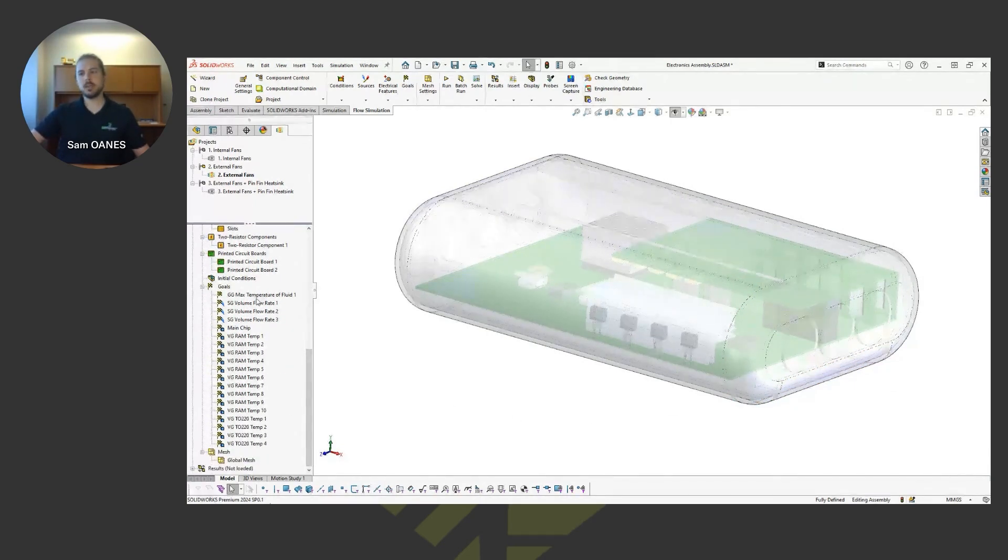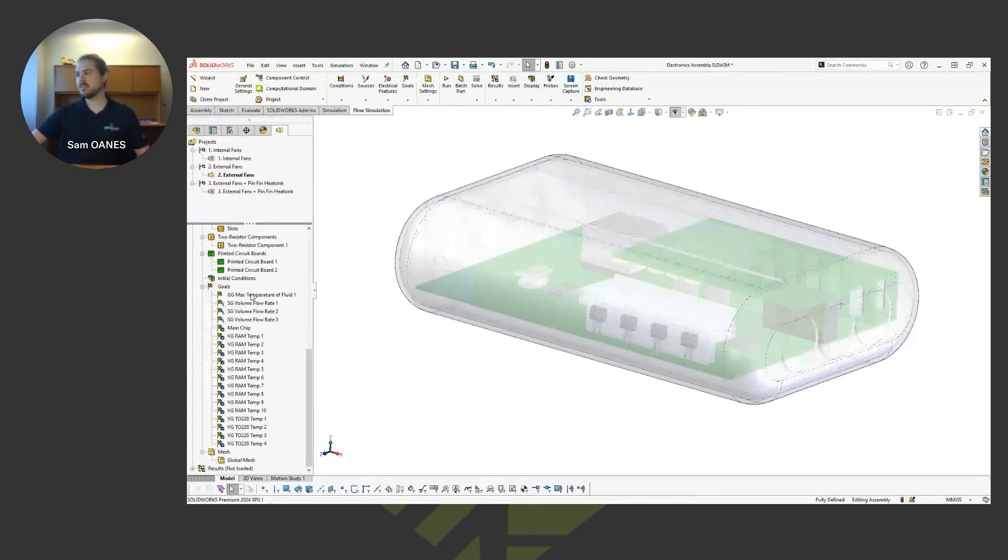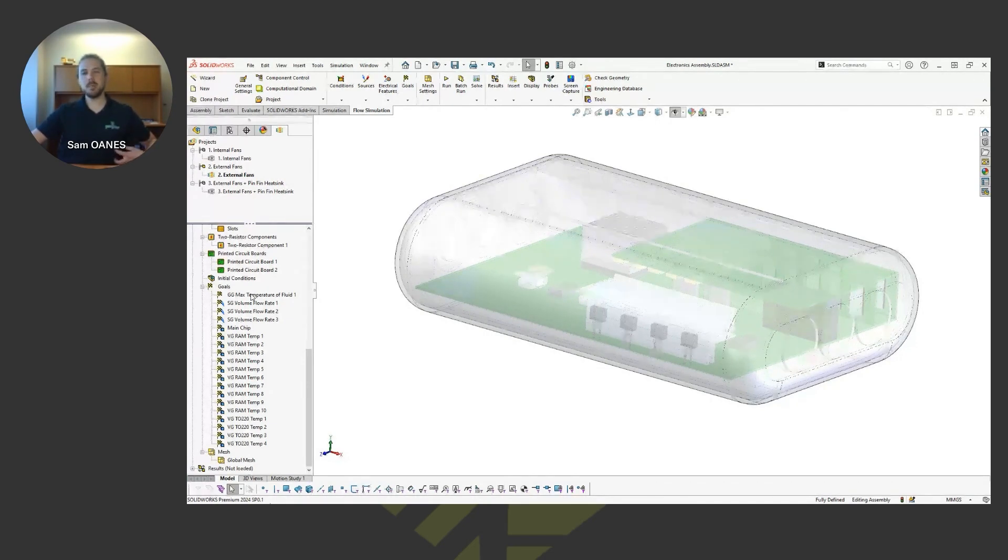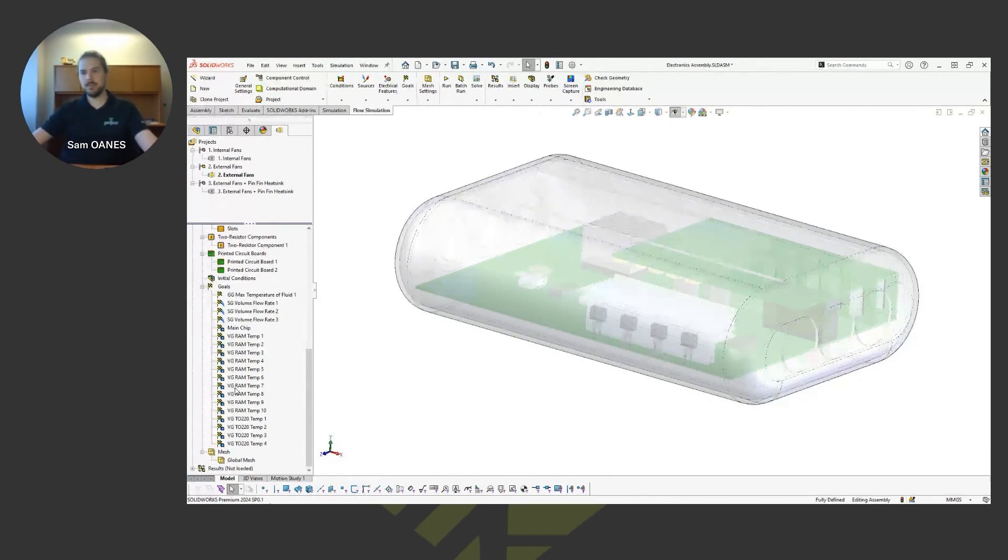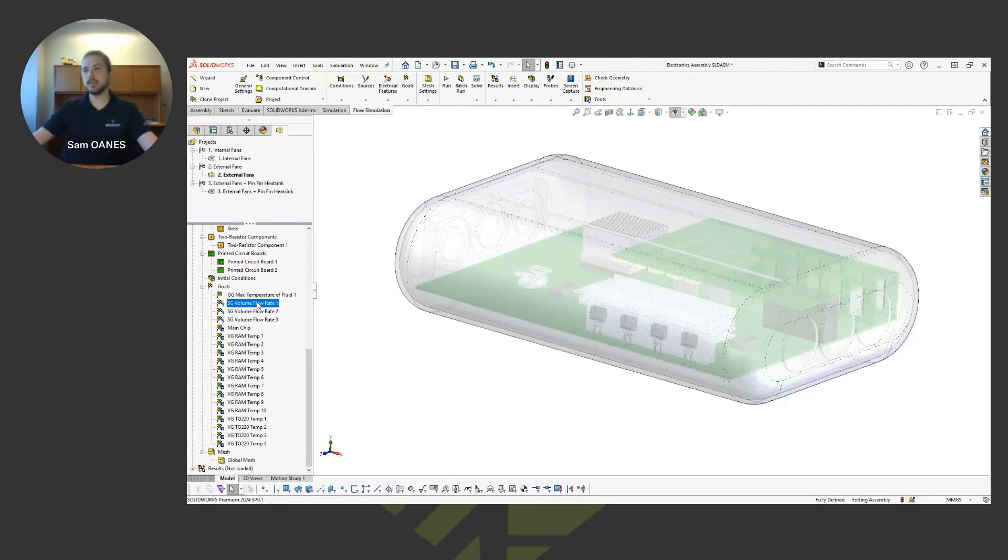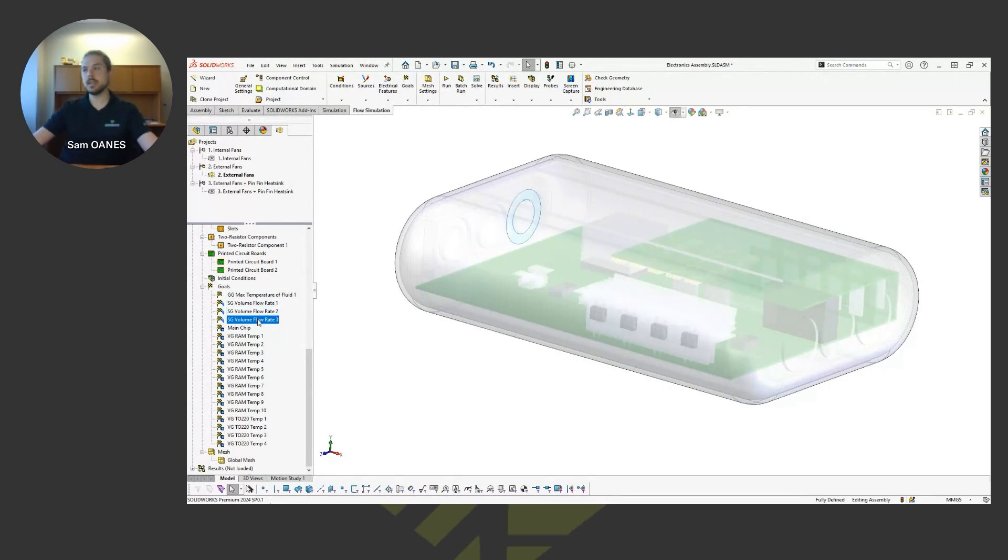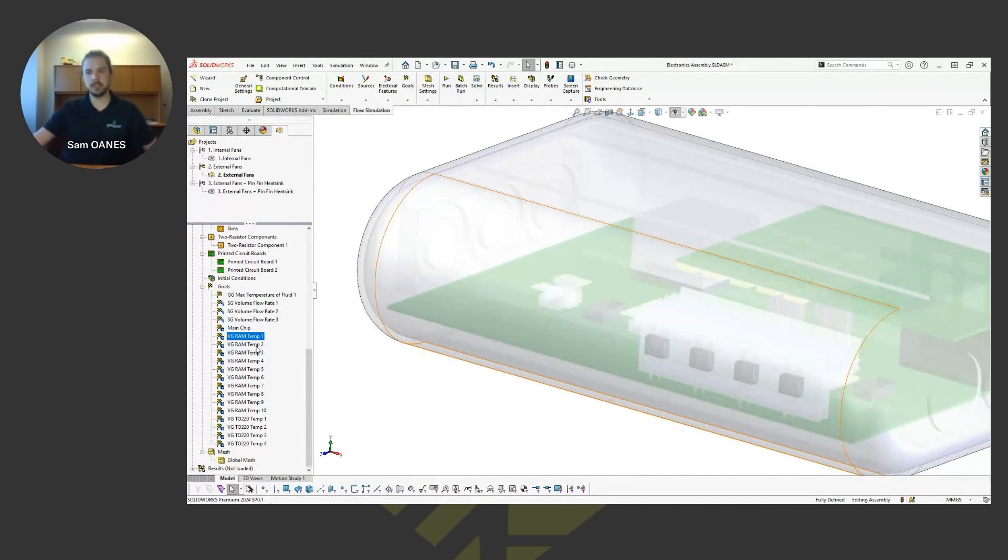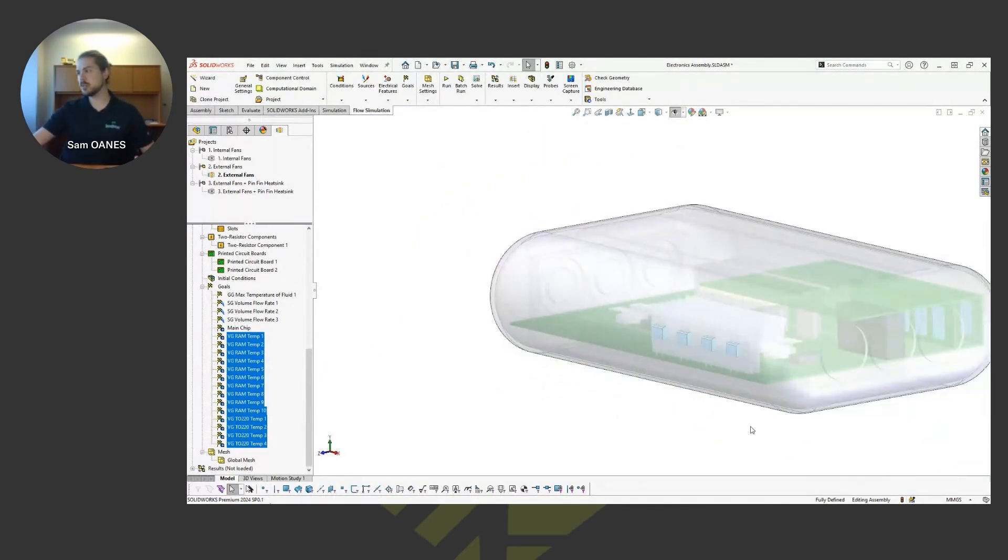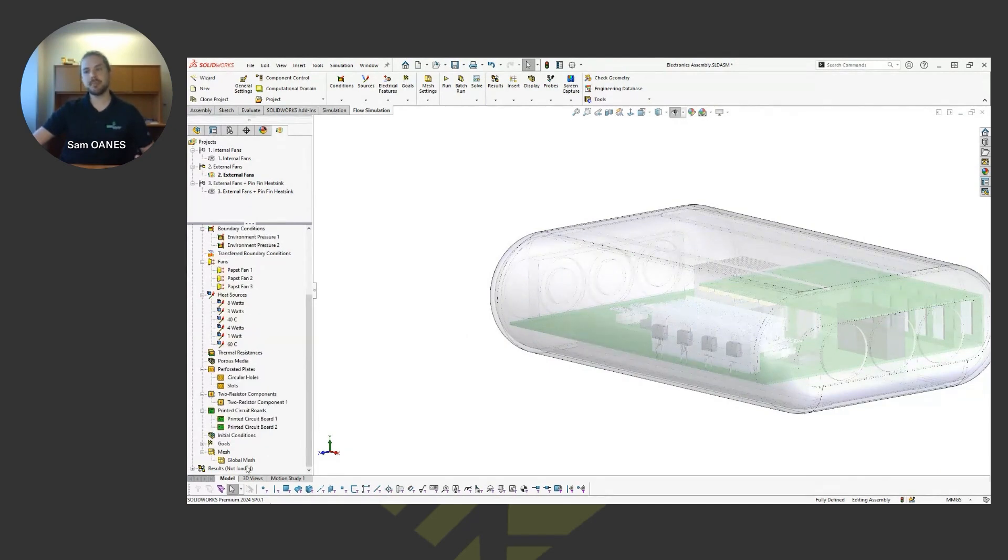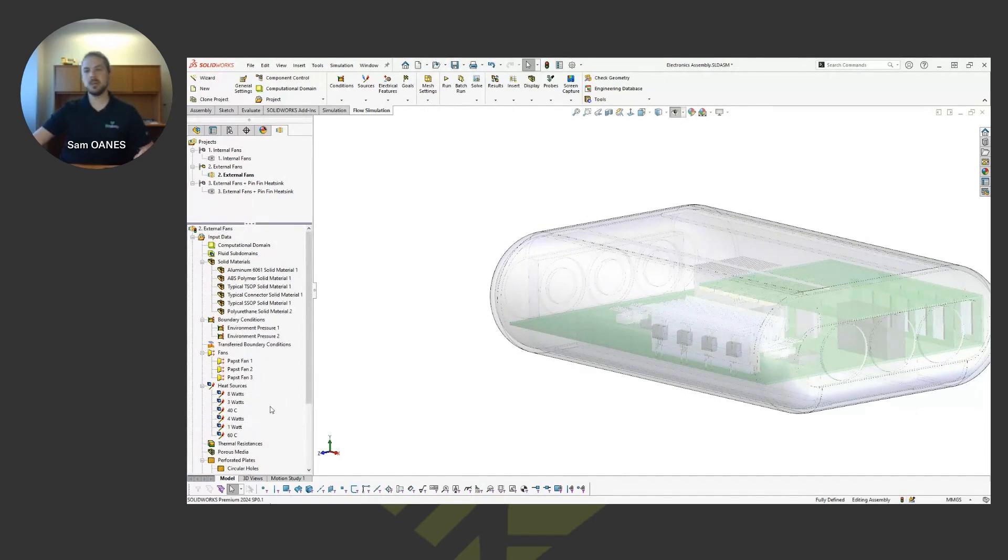After that, we set our goals. I like to describe these as pointing the solver in the right direction. We can think of these as sensors as well. The automated convergence I was mentioning happens with these goals - they define what our convergence criteria is. I've got some temperature goals, some flow rates on those fans. That main chip, I'm tracking the temperature on that, as well as all the temperature on our electric components that we don't want to be getting too hot. It's a great way to track data as well. After that, we let the study run, let the computer do its thing. Now we start doing some post-processing and looking at plots.